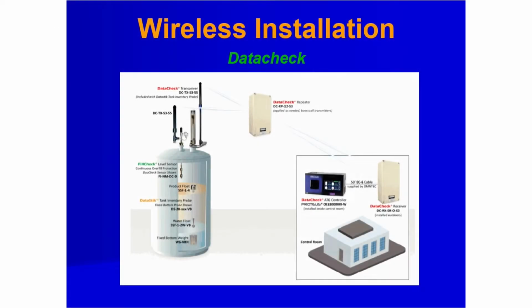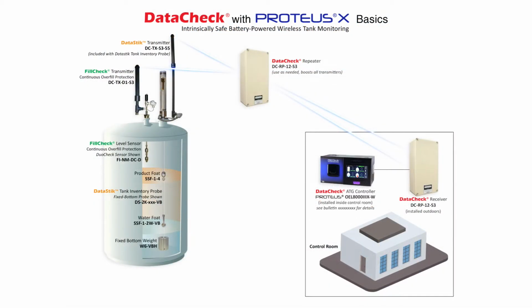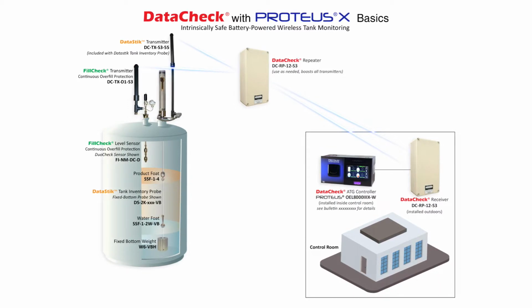In addition to wired probes, OMNTEC also offers wireless systems. DataCheck is our patented ISBPW, intrinsically safe, battery-powered, wireless, tank monitoring system and operates on a line-of-sight principle. It provides high-accuracy inventory measurements, product level, water level, and temperature, and/or overfill protection.